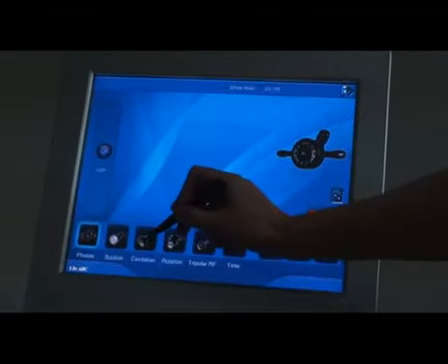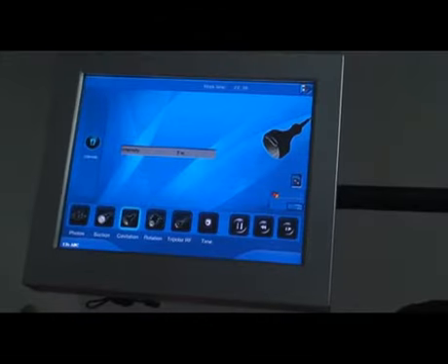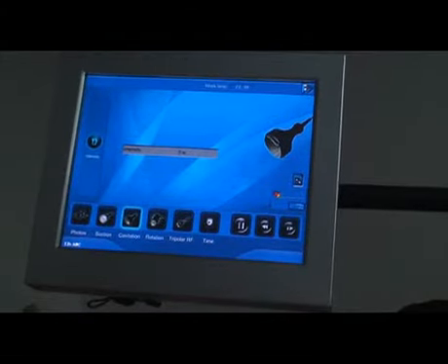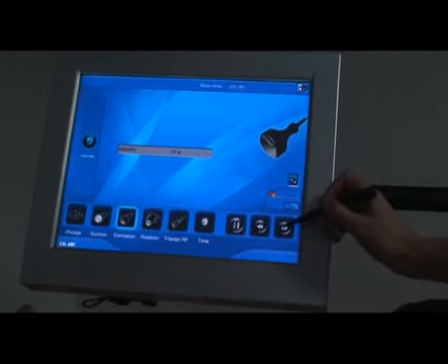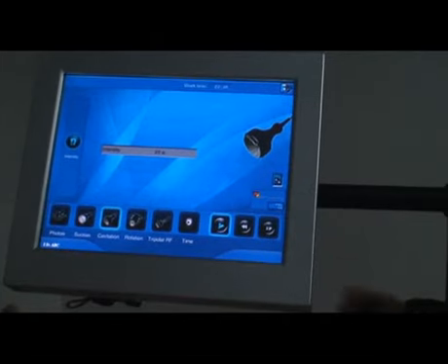Cavitation function. Click Intensity key. Setting output intensity. Click Start. Apply gel on abdomen. Press the foot switch to start treatment. In cycle or in line.